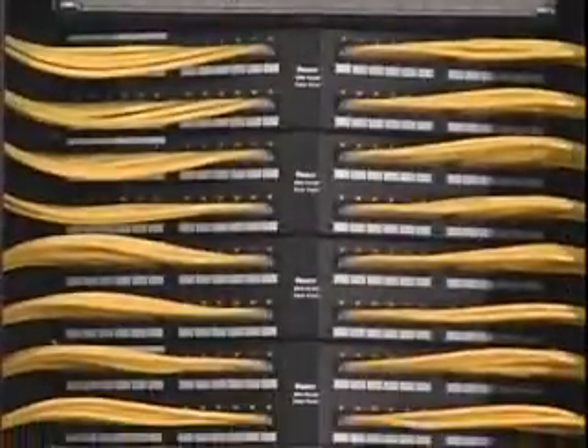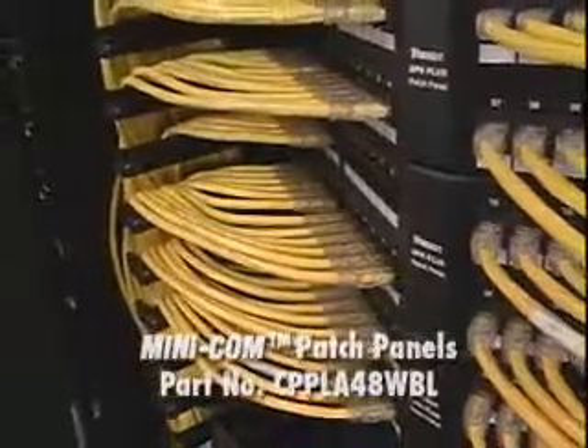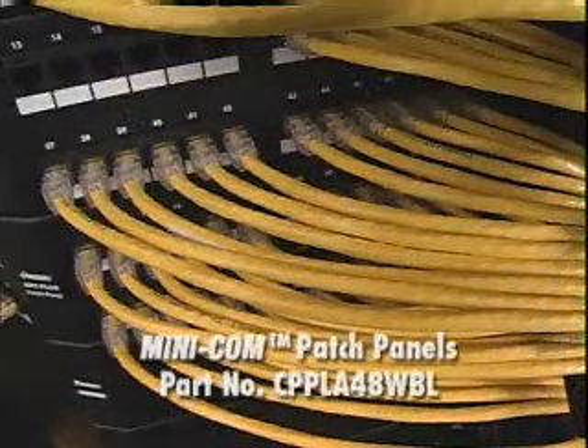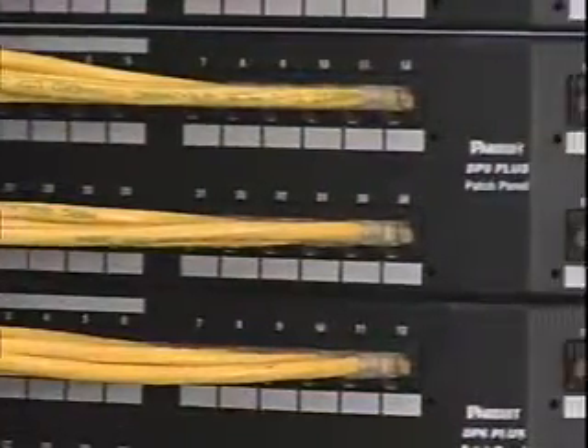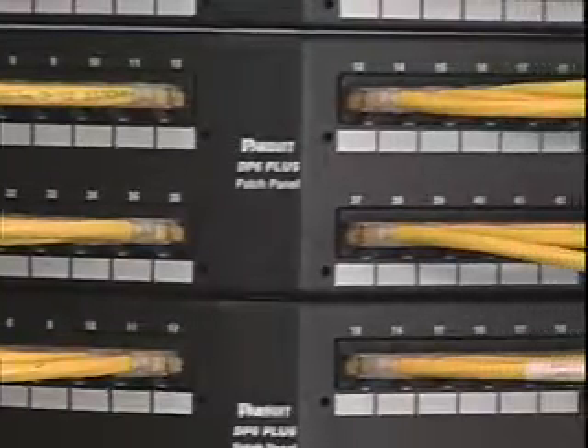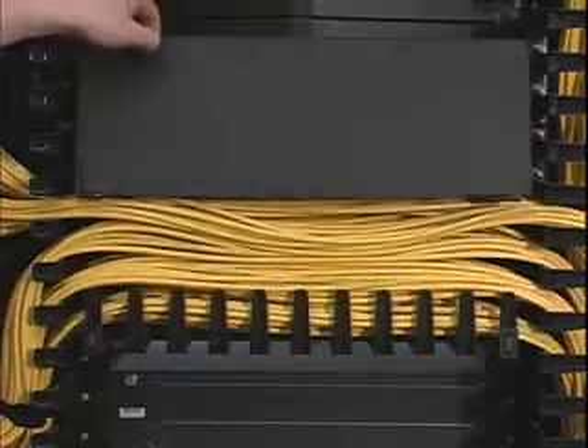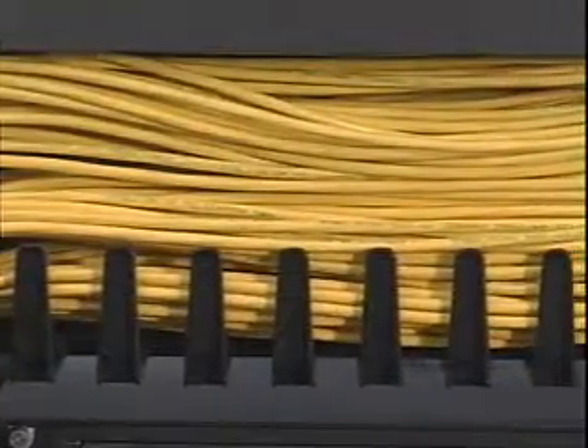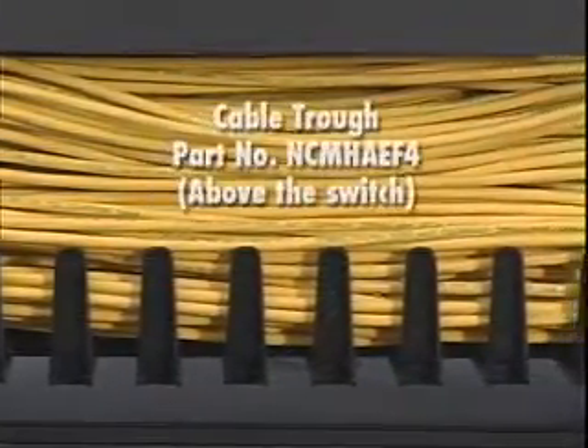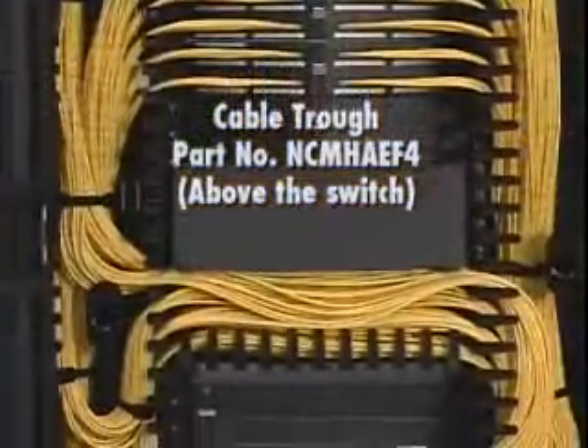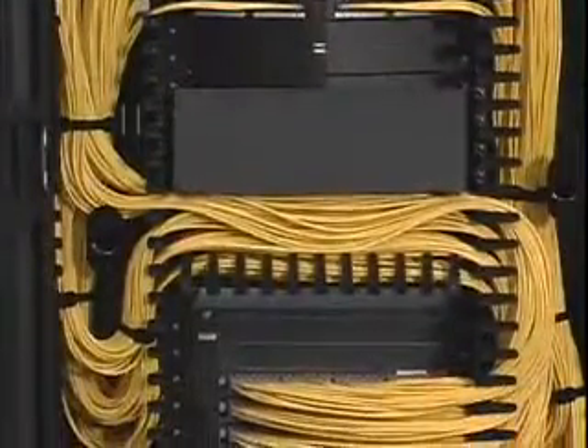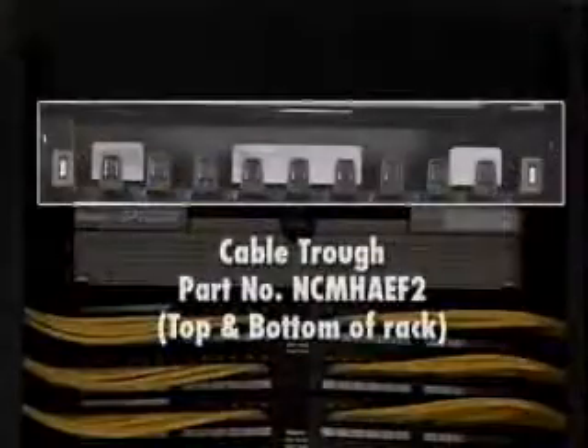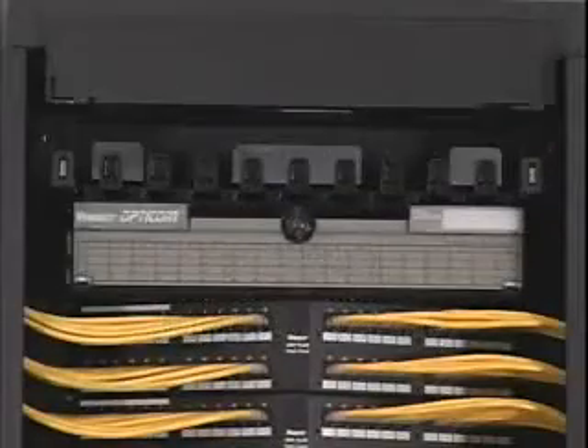The patch panels are PANDUIT Minicom angled modular panels, part number CPPLA48WBL. This panel can support up to 48 ports in 2 rack spaces. For the creation of horizontal cable pathways, the system utilizes PANDUIT cable troughs, part numbers NCMHAEF4, mounted directly above the switch, and NCMHAEF2, mounted at the top and bottom of the rack.